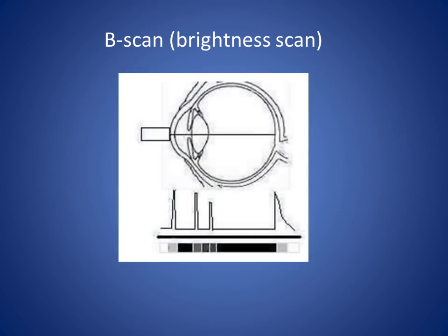In a B scan, the amplitude of each returning signal controls the brightness of a spot, which represents the reflection, the B for brightness giving rise to the name B scan. So a single pulse of ultrasound passing into a series of tissues will give rise to a series of spots, with the brightness of the spots corresponding to the amplitude of the reflection from different layers.